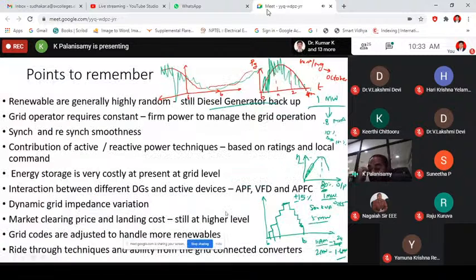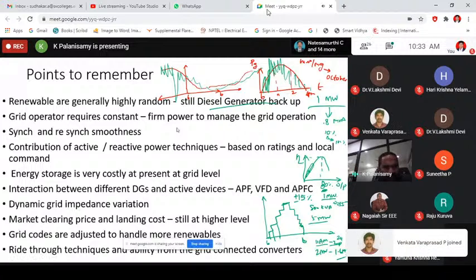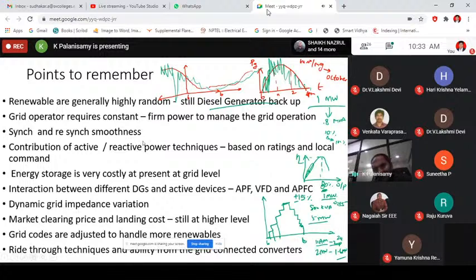So these are the unexpected, or you can say untold truths from the solar manufacturer or the wind manufacturer. For the sake of selling their product, they may say all the things, but internally these are the things that are happening. And the next thing is, in some grid connected inverters, based on the generation or based on the need, it may connect or disconnect from the supply, right? During synchronization and resynchronization, it may connect anytime it wants, and similarly it can disconnect when it finds some problem with the grid.